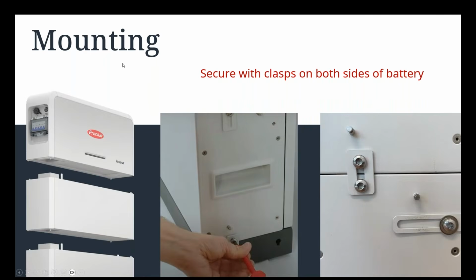Looking at the secure mounting in between the modules. So you stack the module on top of each other, and every module would have this little bracket here, which you need to mount on the left and right hand side of the battery with a T30 screwdriver and a max torque of 5 Newton meters. So relatively simple and quick to install.